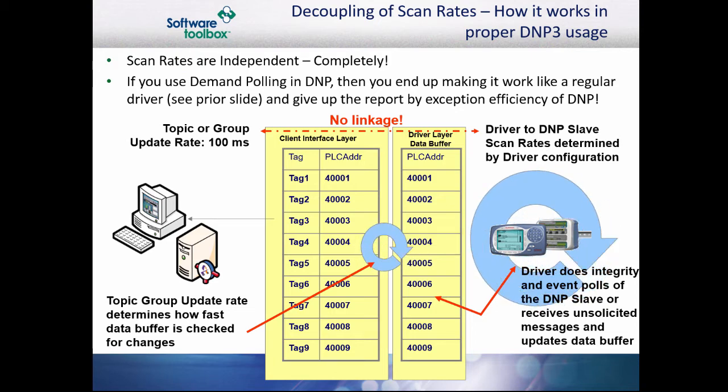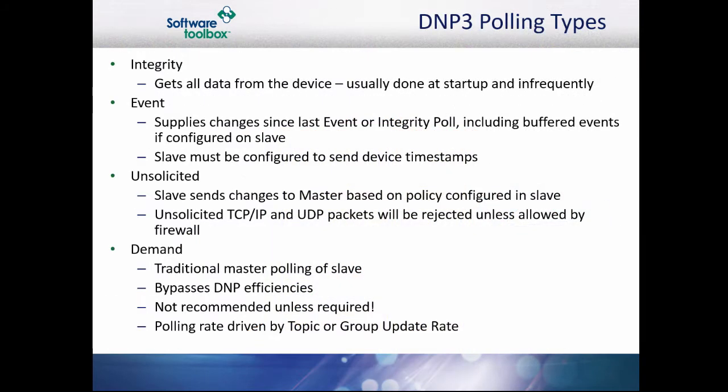There are four types of DNP3 communications. An integrity poll requests all data from the slave regardless of data changes and what the client is asking for. This is usually done at startup and then performed very infrequently after startup. Event polls request all data changes since the last event or integrity poll, regardless of what the client is pulling. If the slave is configured to send timestamps, the timestamps for these events will come from the device.